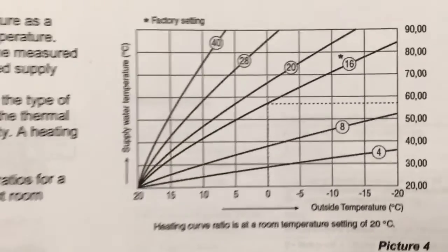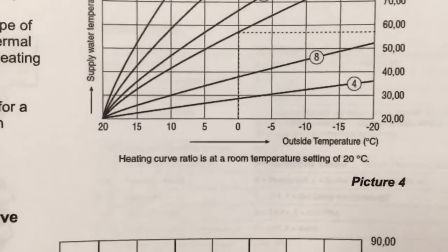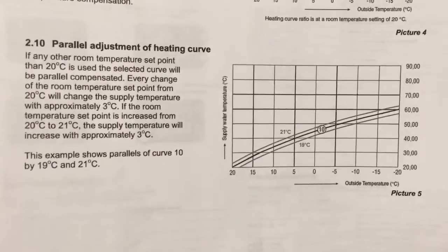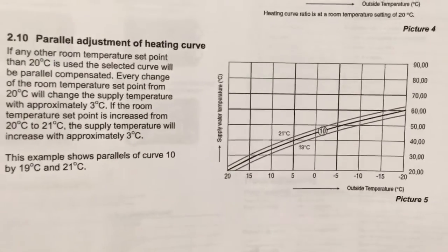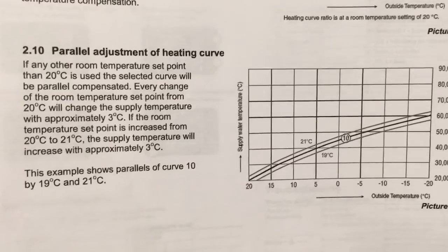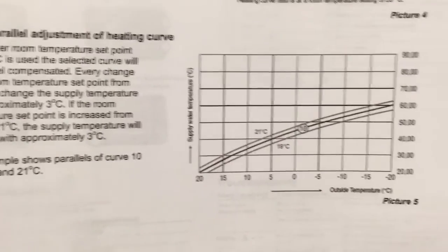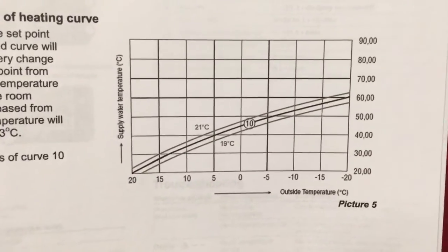This says it's basically the heating curve ratio is at room temperature setting at 20 degrees, which we've got the thermostat set to. But what it mentions down the bottom is parallel adjustment of the heating curve. So for every degree you go up and down, it changes the supply temperature approximately three degrees Celsius.